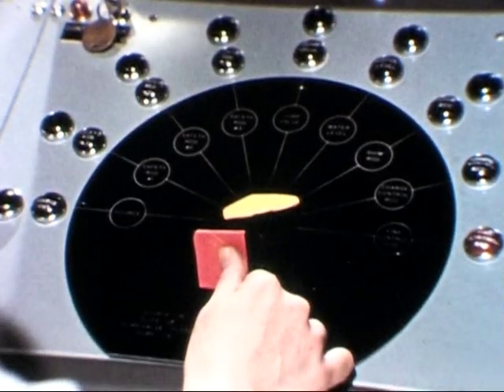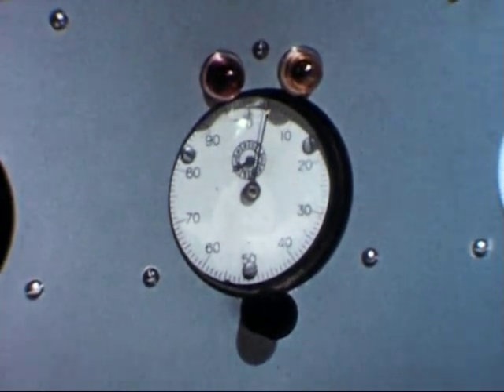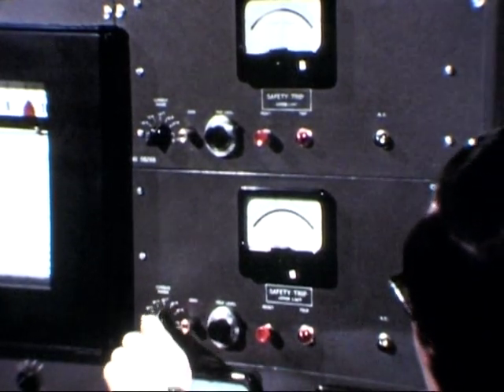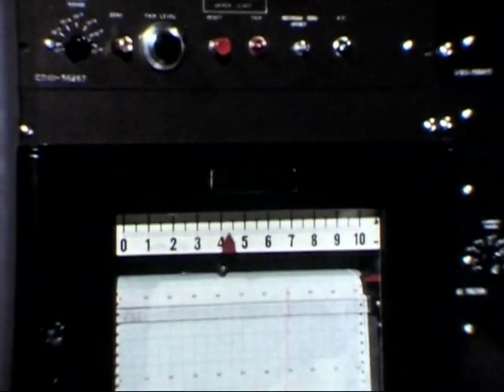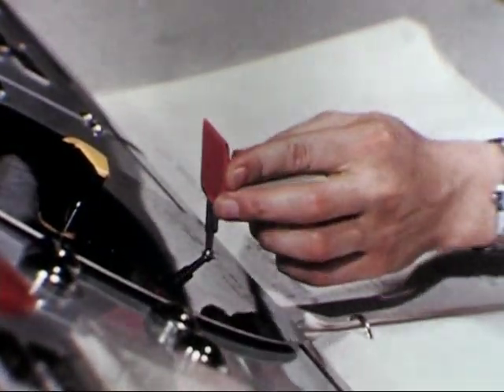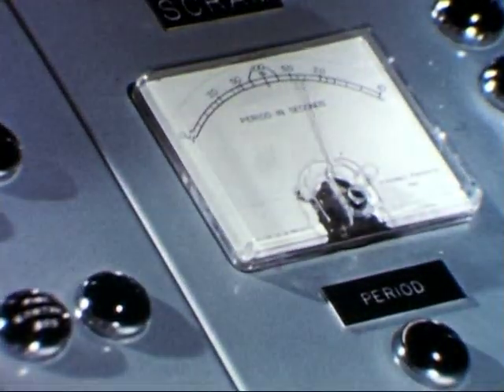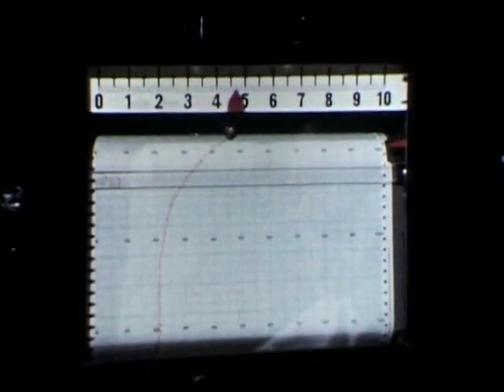With the shim rod completely withdrawn, the coarse control rod is next. As startup proceeds, the neutron level is automatically and continuously monitored. Any one of four safety circuits can shut the reactor down, and scale changes are necessary as startup continues. As the fine control rod is withdrawn, the multiplication gradually increases. The exponential rise on the chart indicates that criticality has been reached.